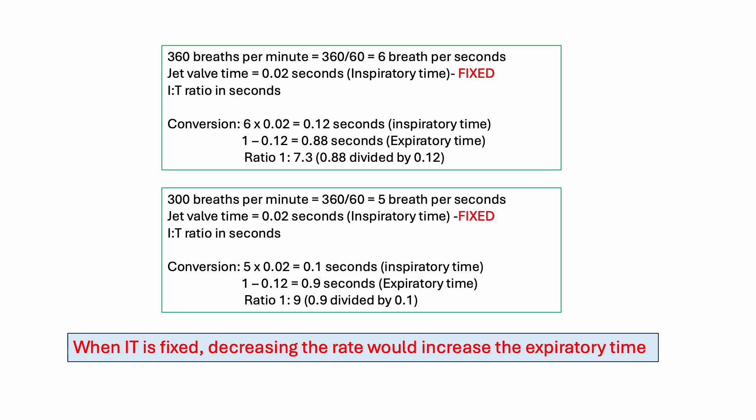The concept to remember is that in jet ventilation, the inspiratory time is fixed at 0.02 seconds. So if you decrease the rate, the expiratory time increases because the inspiratory time is fixed. When you decrease the rate, the expiratory time goes up to compensate.